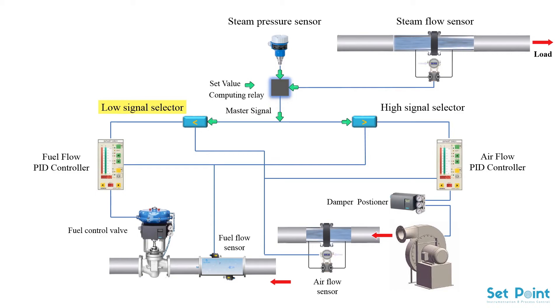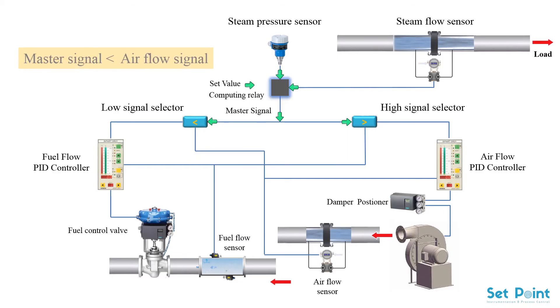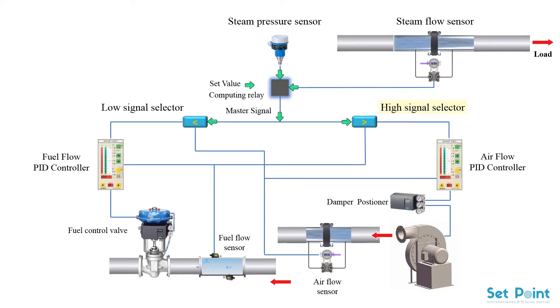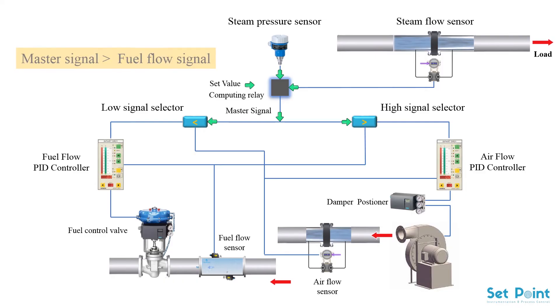In the low signal selector, the master signal is compared with the signal representing the air flow. The selector passes the master signal only if it is lower. In the high signal selector, the master signal is compared with the signal representing the fuel flow. The selector passes the master signal only if it is higher.